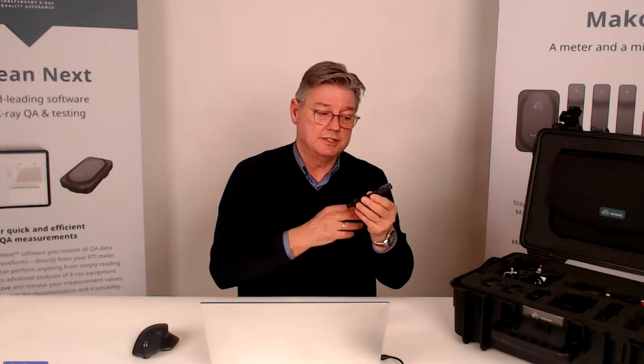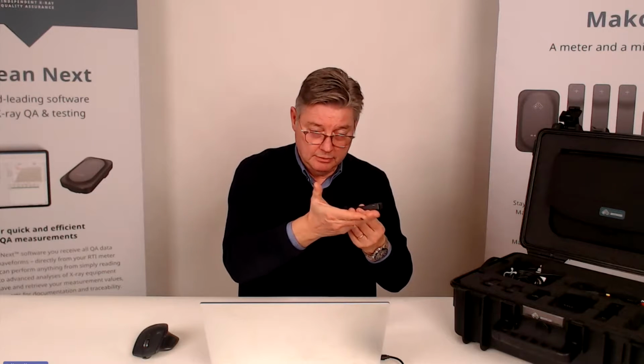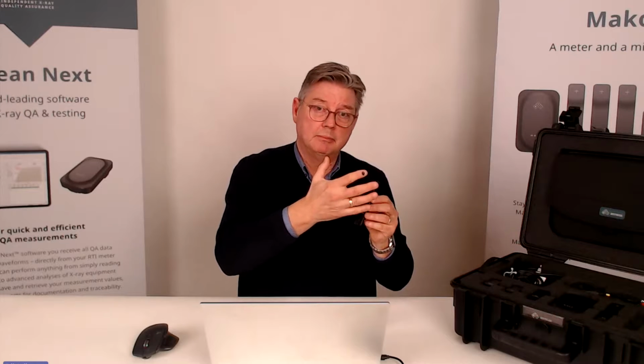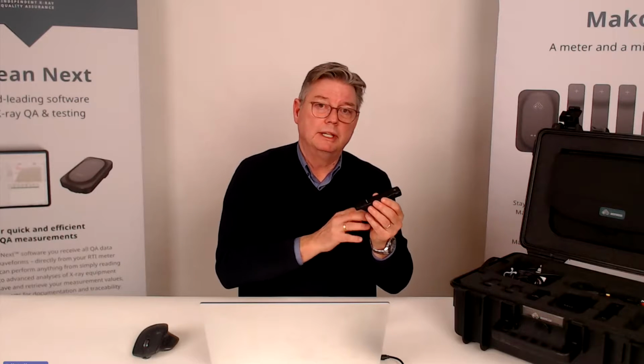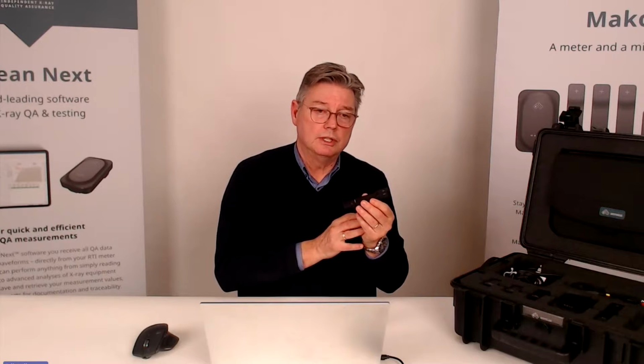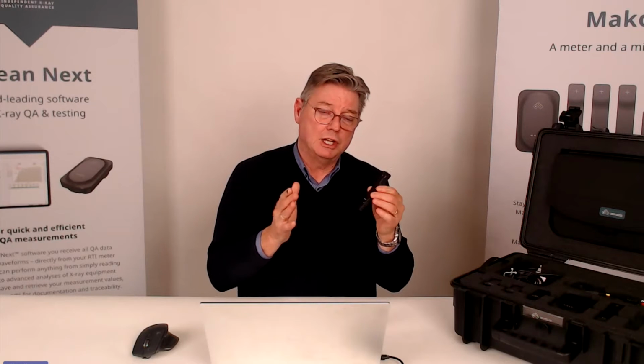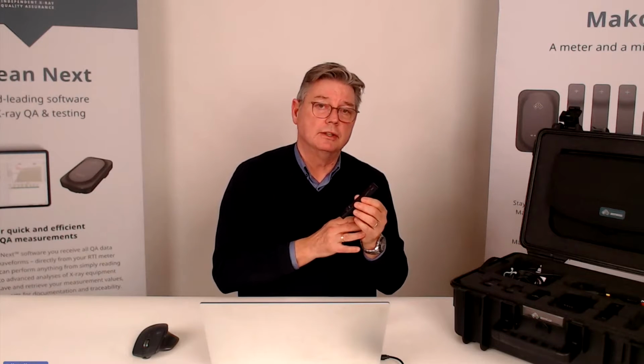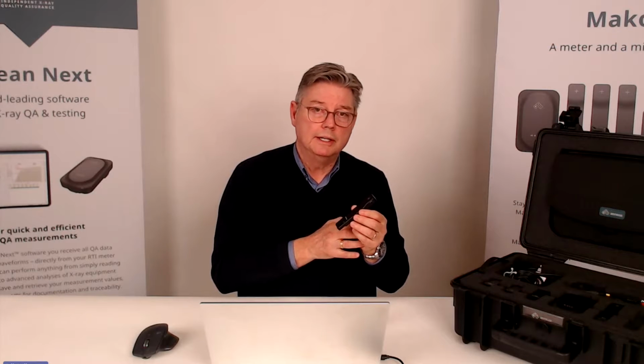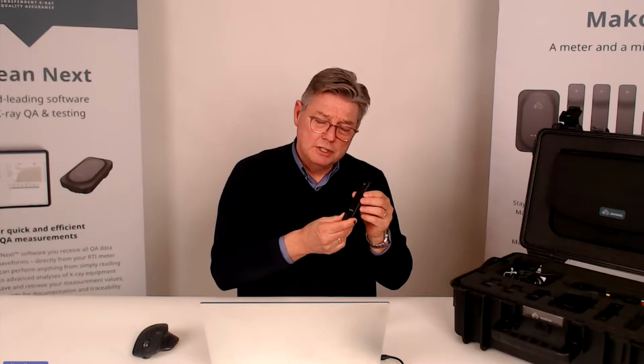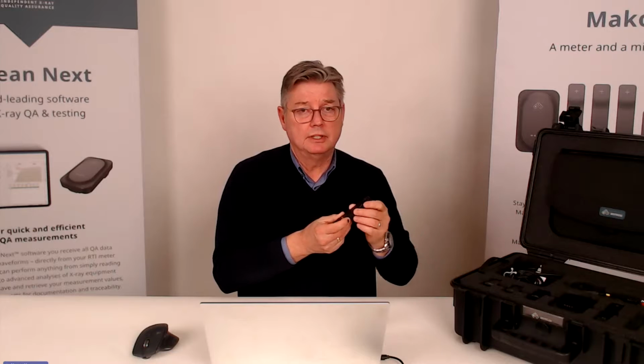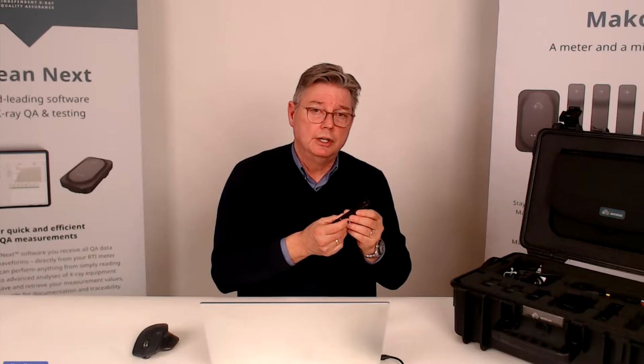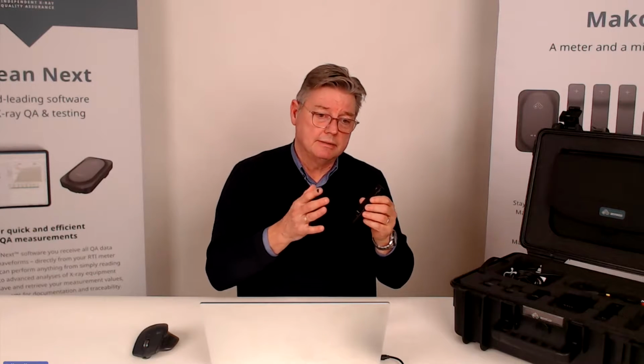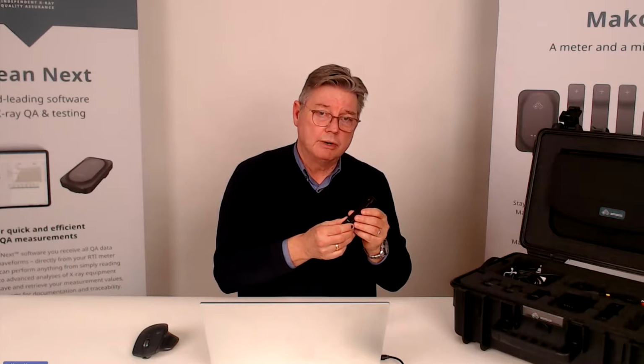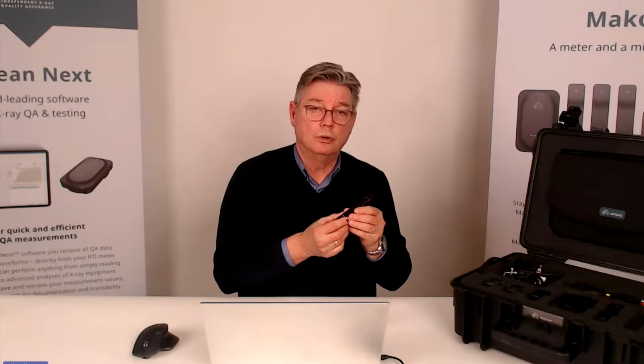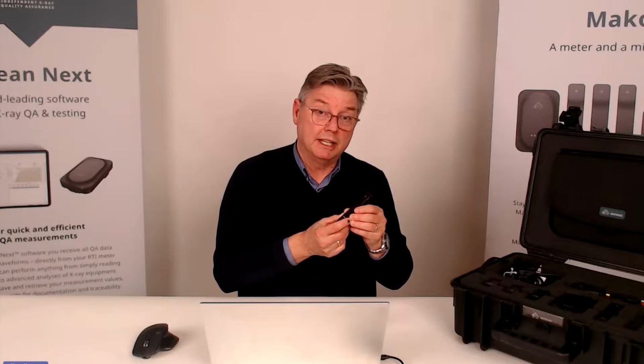Although the form factor is the same, you'll see the thickness, the detector is layered, it's segmented. The filtering in between is a little bit different, so as to manage the low energies and the peculiarities of a mammo spectrum. There is a third detector. I didn't have it here, but it's a dental detector, which has a limited kV range, which is suitable for dental applications.